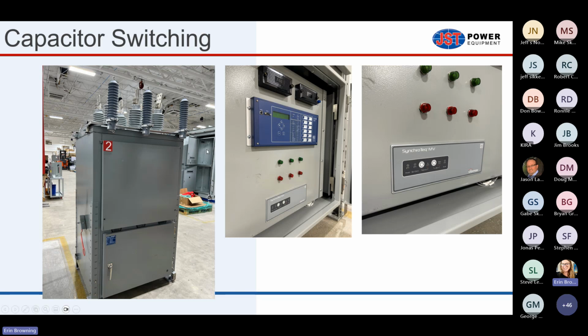And this is a test unit. There's voltage sensors attached to the roof of the test unit. There's a Schweitzer relay for protection and control, and then there's a third-party zero cross relay. And this is a VisiMax control. Schweitzer also has their equivalent, but for the case of this test, we used VisiMax. So basically, the blue relay is for protection. That's what's measuring overcurrent or under voltage or whatever protection elements the customer is using in their relay.